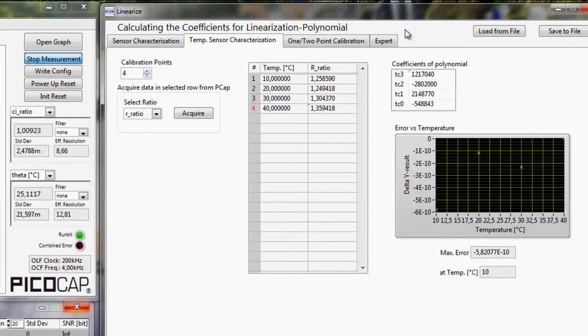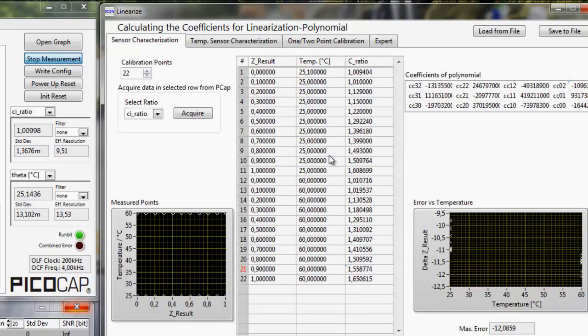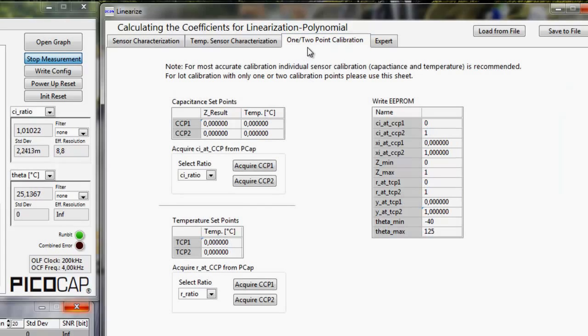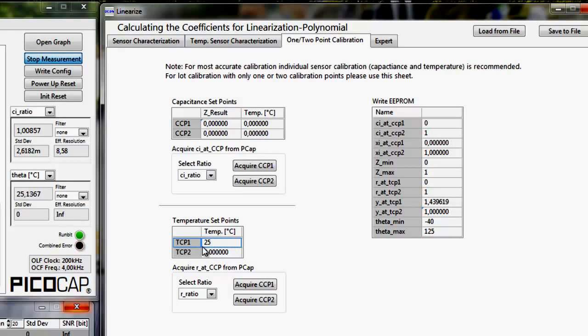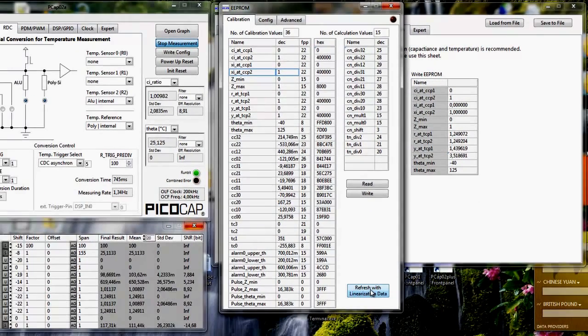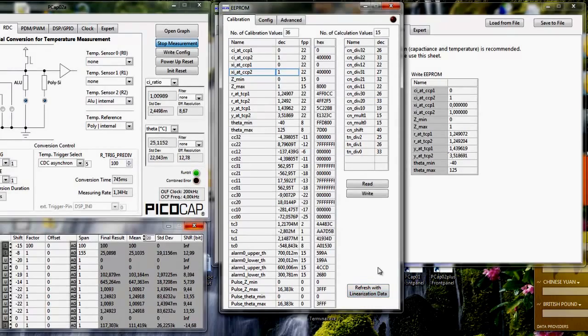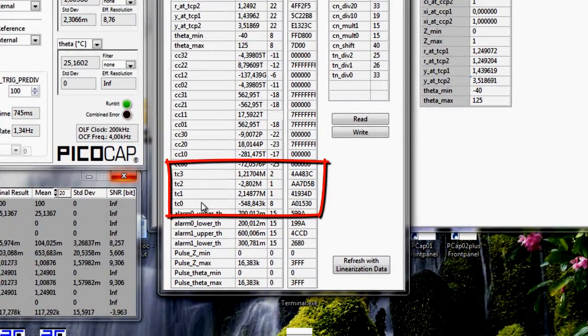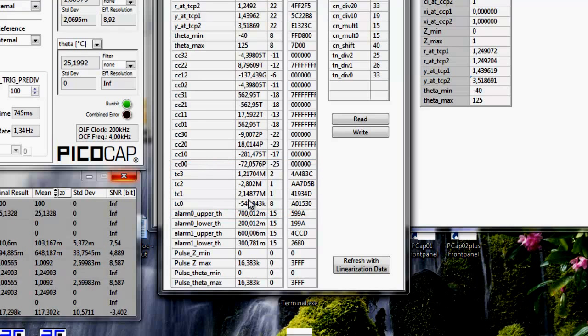And all you need to do then would be, when you do the capacitance linearization anyway at any 2 temperatures, for example like here 25 centigrades and 60 centigrades, you use that one and 2-point calibration tab, and when you are at 25 degrees centigrades you say acquire CCP1, and you see it's automatically filled in here. And when you then at the next temperature, in my example 60 centigrades, I say acquire CCP2, and the second ratio is filled in here too. That way the standard coefficients used for the internal temperature sensor linearization are 2-point calibrated. Of course I need to refresh the EEPROM parameters again to match this new calibration, and you see then TC3 to TC0 is adapted accordingly. So that way you can also do the temperature sensor linearization in a more simple approach.